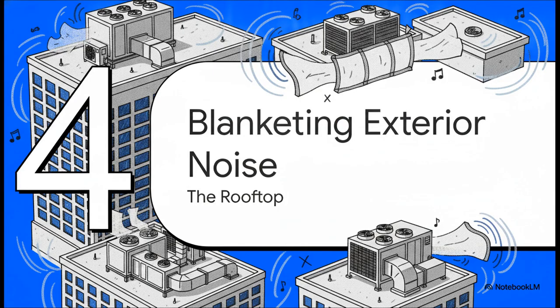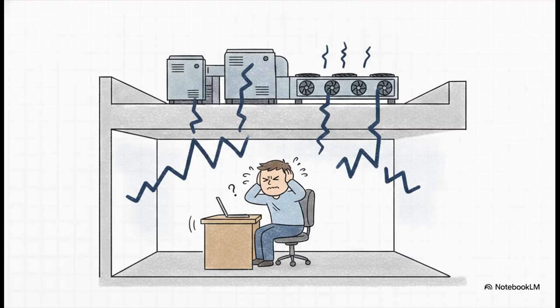Finally, we've made it to the top. Section 4, Blanketing Exterior Equipment Noise. The rooftop. Let's climb all the way up to the roof to deal with the source of some of the absolute most stubborn vibrations and mechanical sounds in the entire HVAC world. Now, even though engineers design modern rooftop equipment to be as quiet as mathematically possible, outdoor machinery, like refrigerant compressors, big packaged units, and air-cooled chillers, still generate residual noise. There's just no way around it.